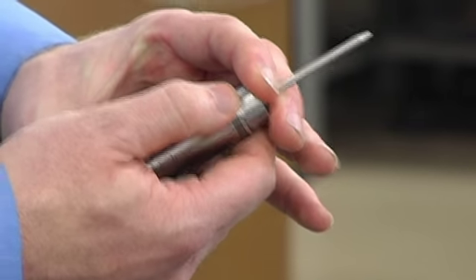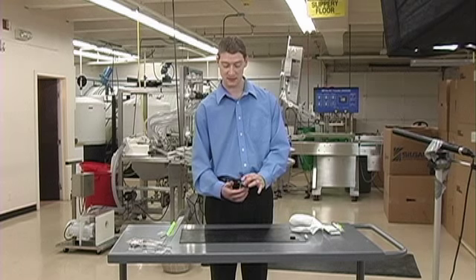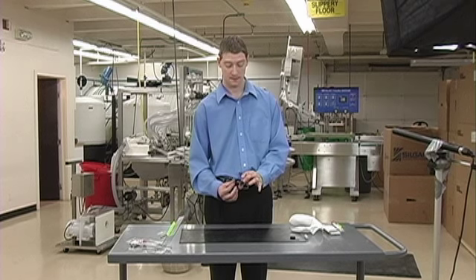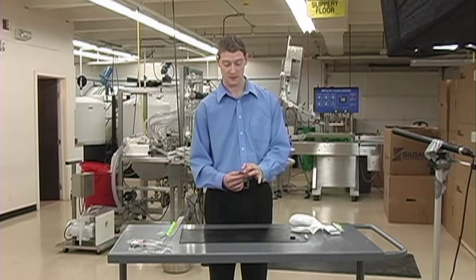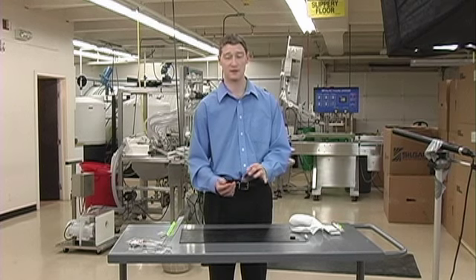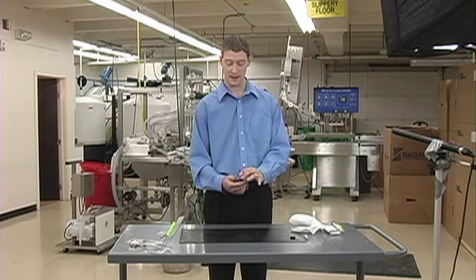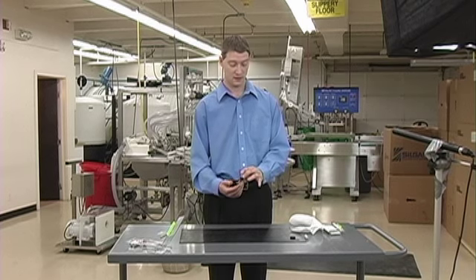The other thing you should know is that this O-ring seal is designed to only be used once. The seal design affects the O-ring so that it can't be reused once the data logger has been opened. So make sure to only open the data logger if you're changing the battery, and if you do have to open it for any other reason, make sure you change the O-ring. This is very important if you're using the data logger in an autoclave or some sort of pressurized or vacuum environment.